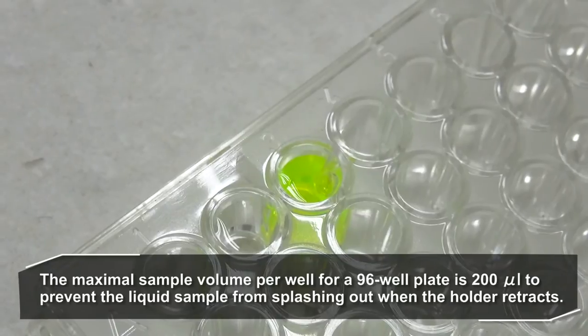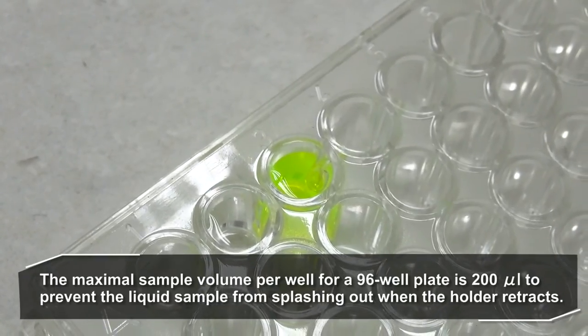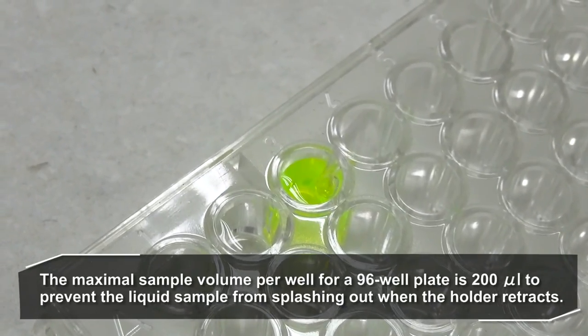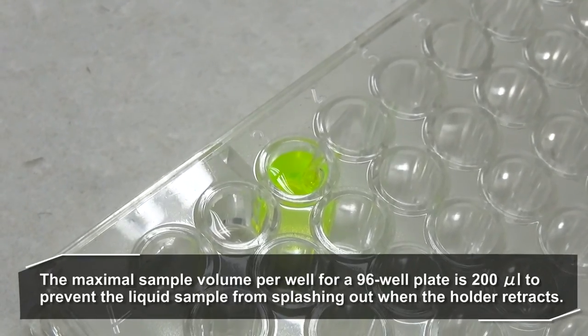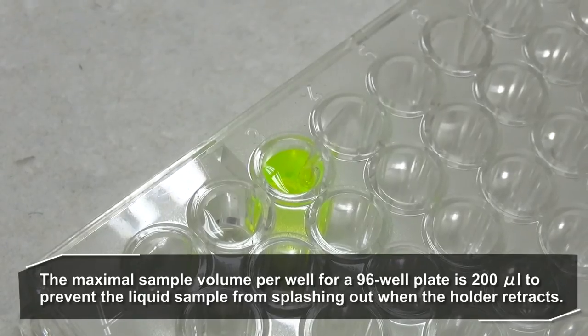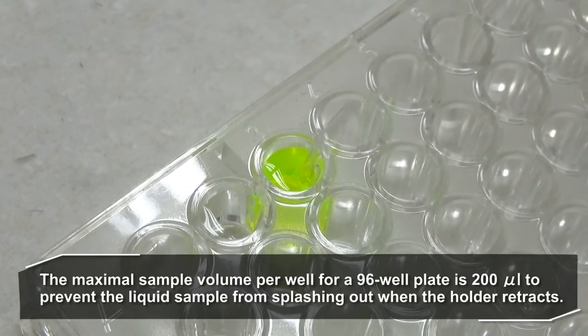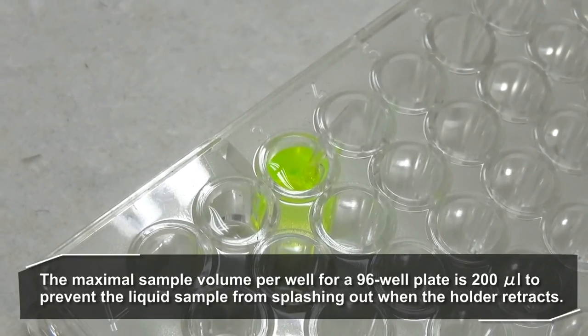The maximal sample volume per well for a 96 well plate is 200 microliter to prevent the liquid sample from splashing out when the holder retracts and from damaging the internal part of the spectrophotometer. If the liquid does splash out, clean up immediately.